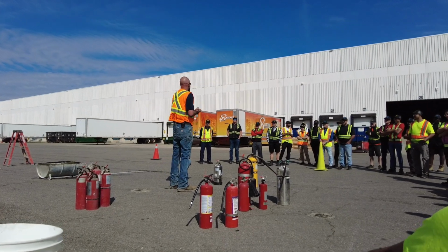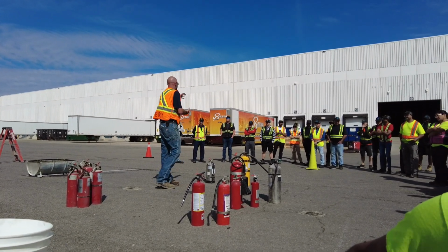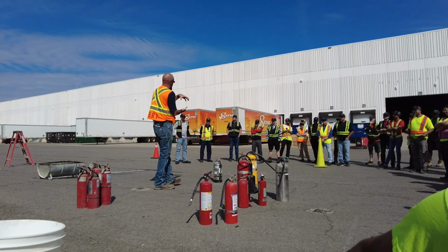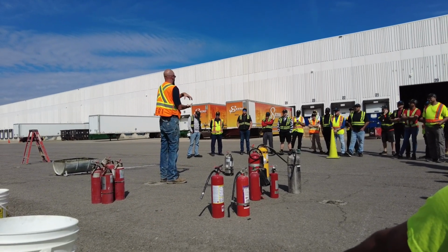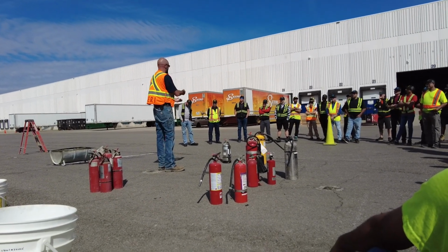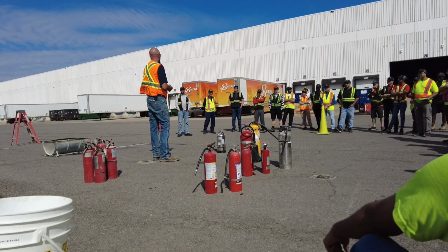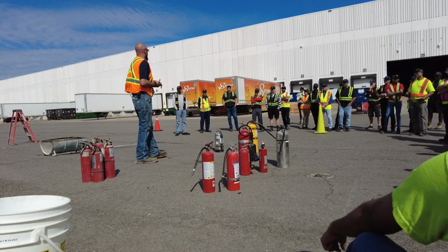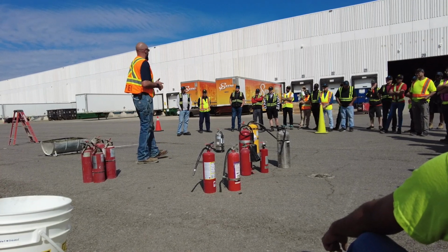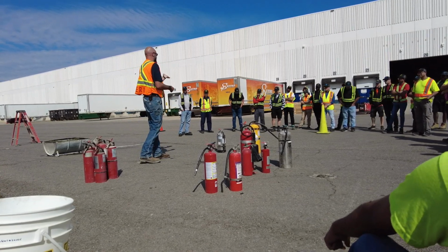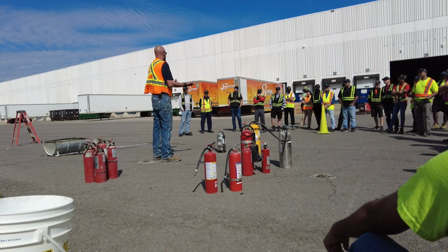I can't guarantee that they'll work. The problem is you've got that nitrogen that sits there and pushes on that chemical for years and years and years. And we've had it happen where people have squeezed them and nothing works, and the gauge still says full. So that's why we do a regular check. Every 6 years they come out, they get emptied, and we make sure that the gauge actually works.